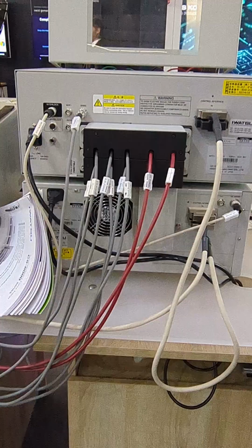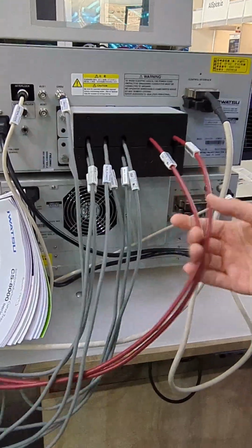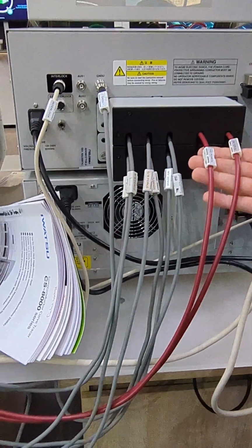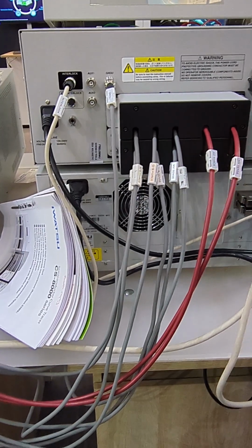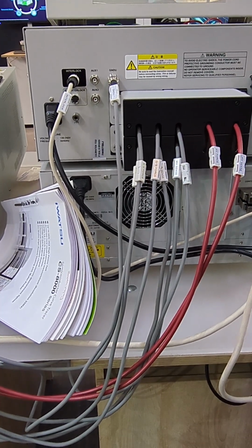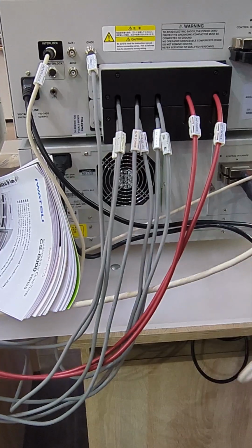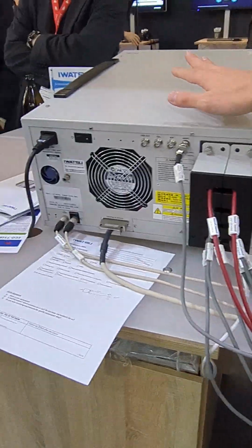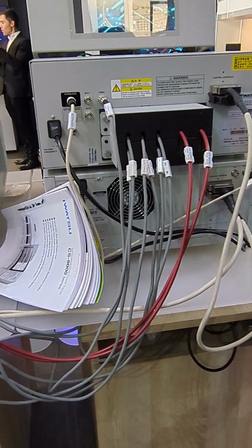Yeah, this is just some triax cables for the Kelvin sense measurements also. And then we have for the high voltage some different cables. I don't have the name in mind, sorry for that. And then we have here just the control interface cable. So the main thing is always the control unit, the master unit, controlling the test fixture and the high current unit. Yes. And then everything is controlled via this one.